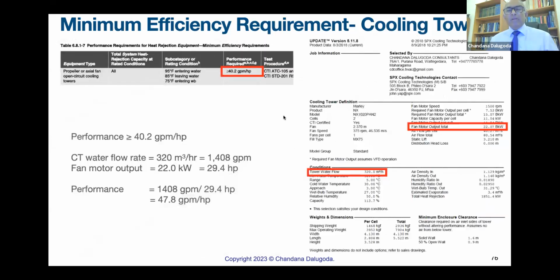What does it mean? I have a little example. This is a cooling tower which we selected for a project. The cooling tower water flow rate is 320 cubic meters per hour and fan motor output is 22 kilowatts. So if you put it to this format, a cooling tower water rate of 320 cubic meters per hour becomes 1400 GPM. 22 kilowatts become 29 horsepower. Final result is 47.8 GPM per horsepower, well above 40. So this complies with the requirement for the cooling towers.